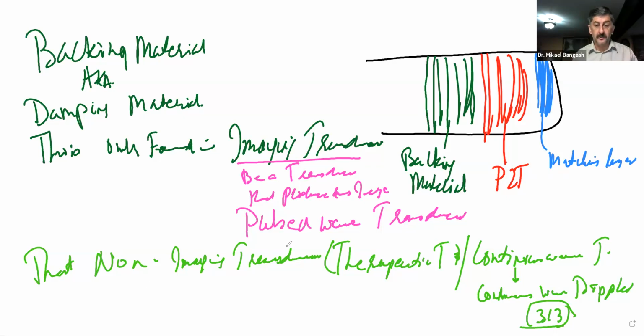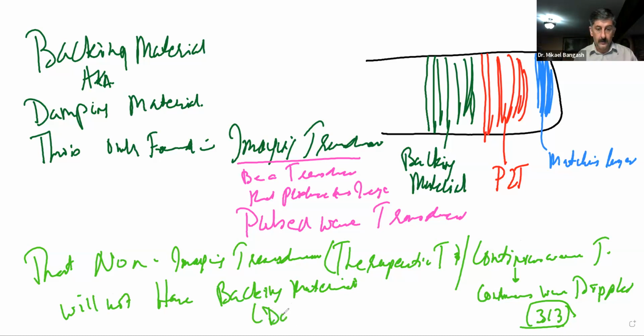What about these non-imaging transducers, which could be a therapeutic transducer, or a continuous wave transducer, or even what we call continuous wave Doppler transducers? They will not have backing material, or what we can more correctly call damping material. Clear?